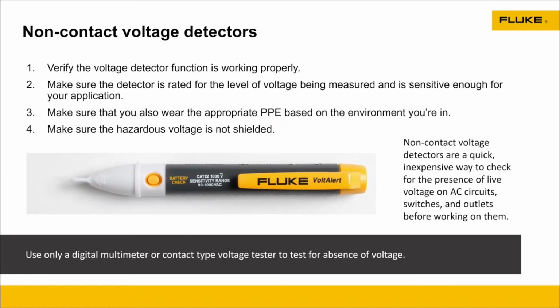Now also, there are times where you might need to use a non-contact voltage detector. These are great. They allow you to at least verify that you have voltage there. The light comes on, it detects it. Sometimes they will buzz, depending on which model you have, but it is a good indicator that you might have live voltage present. But if you're looking for the absence of voltage, you always need to use a test lead. Make sure you make contact with your test leads to verify that the voltage is down, because what if you have shielded cable? Maybe it's not reading it, you get a false negative, and then you get shocked. So that's kind of the key one on that.